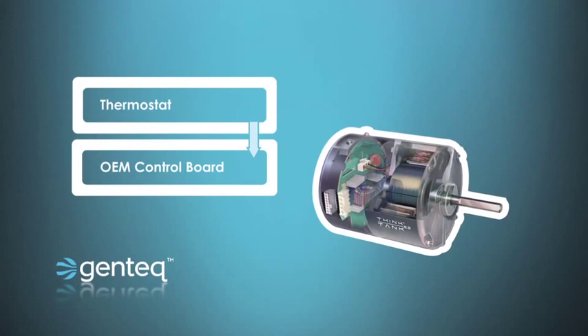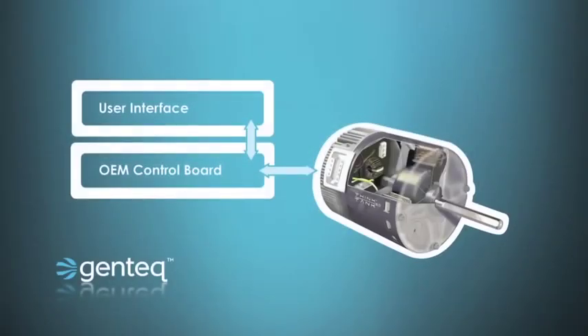Many manufacturers today have integrated those two circuit boards into one board, so the thermostat tells the main board what demand you're in, and on the main board are all the selections for airflow and comfort, which then sends communication down to the motor. There is one more latest and greatest technology: communicating systems. In a communicating system, the thermostat — sometimes called a user interface — can be used to program airflow and comfort settings in menu selections on a digital screen, where you program it like a phone or handheld device, sending a digital signal to the control board and then down to the motor.